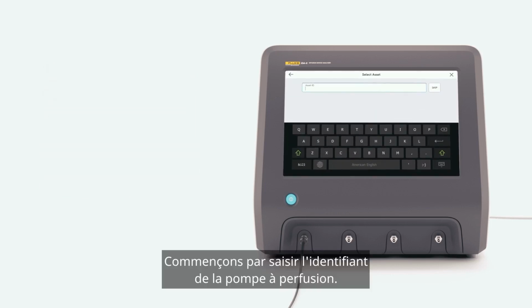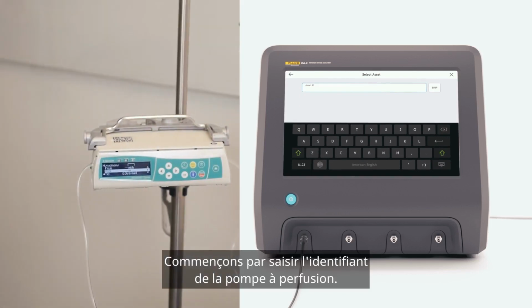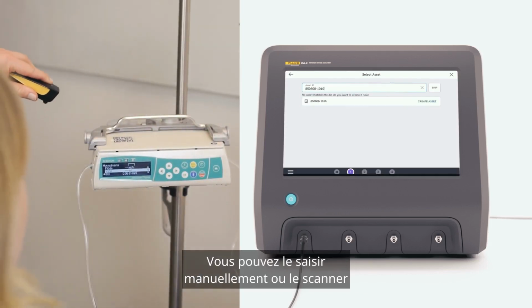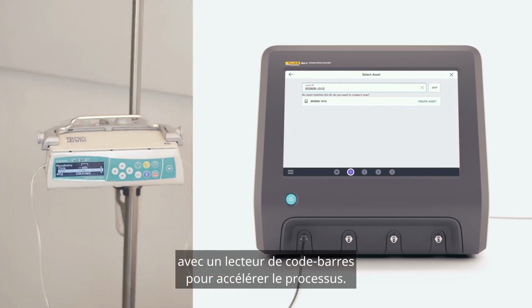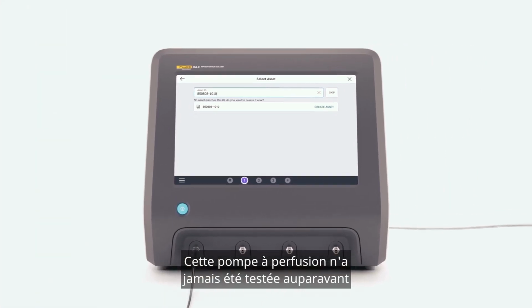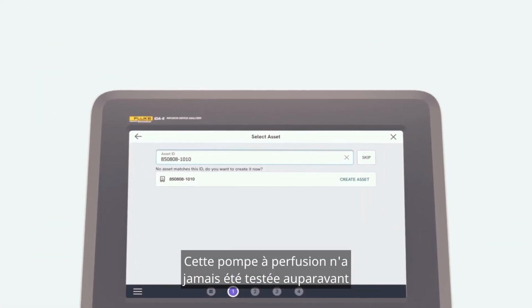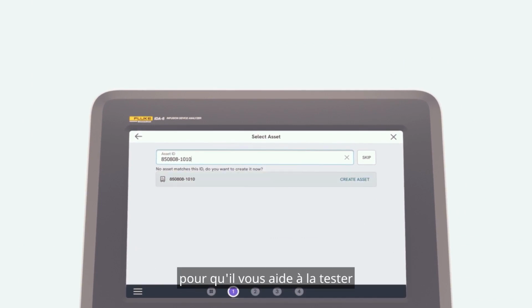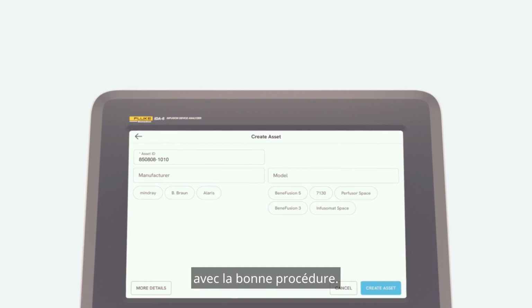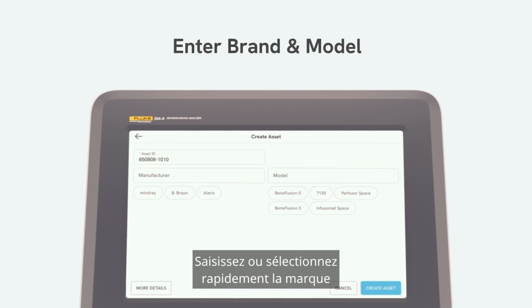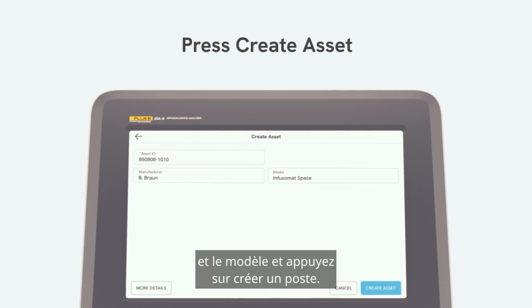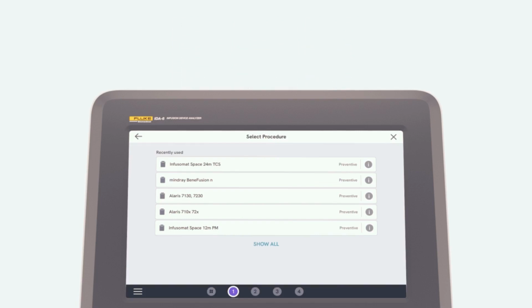First, let's enter the asset ID of the infusion pump. You can enter it manually or scan it with a barcode scanner to make it even quicker. This infusion pump has never been tested before, so you are given the possibility of adding it to the system to let it help you test with the right procedure. Enter or quick select the brand and model and press Create Asset.